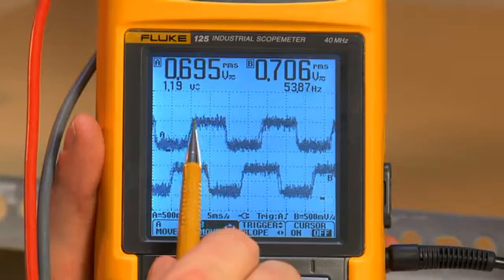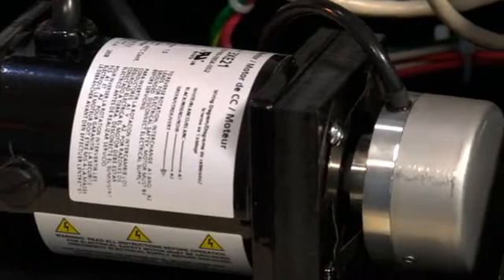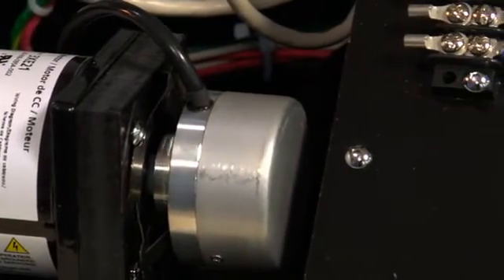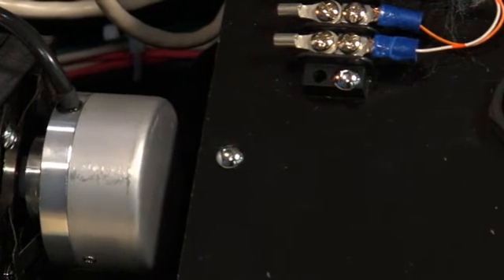Excessive noise is our likely culprit. Upon inspection of the cabling, we find that the cable shield at the controller wasn't fastened down properly.